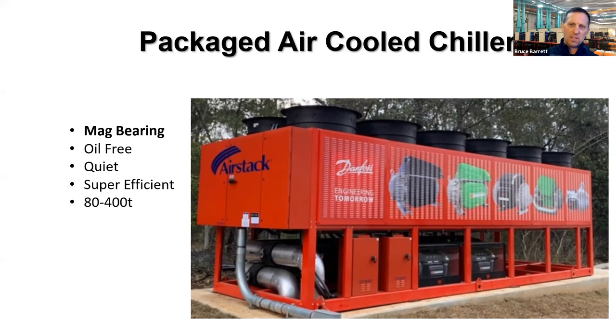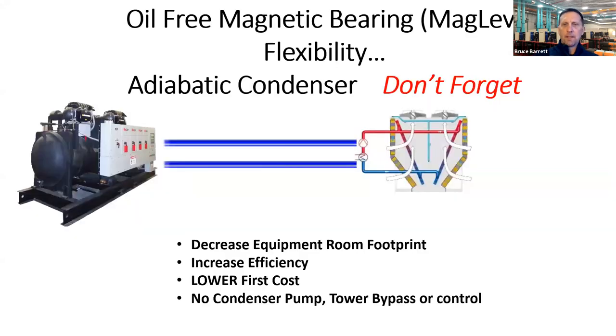This particular photo is just showcasing some of the alternative refrigerants that we already do offer. Standard EC fans, it's a super, super quiet machine. Very efficient. Don't forget, a couple weeks ago we talked about the flexibility of the mag bearing opportunity. We can have an indoor evaporator, controls, and compressors, with refrigerant piping out to a condenser, which could be adiabatic, lowering the amount of lift and work those compressors do. Very, very efficient, very low water usage, no tower pump, no tower bypass control.